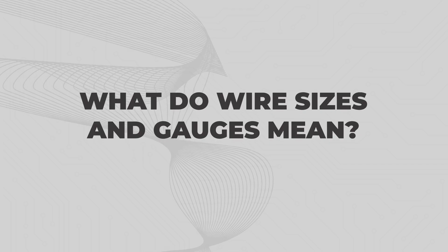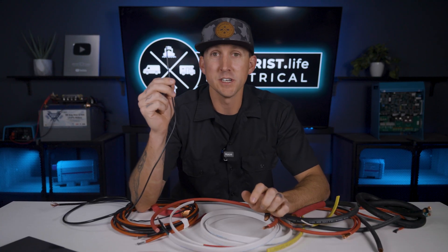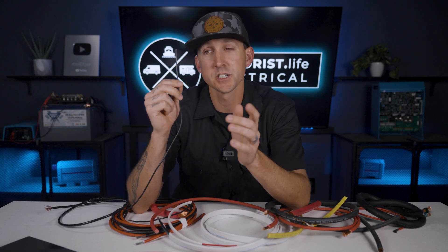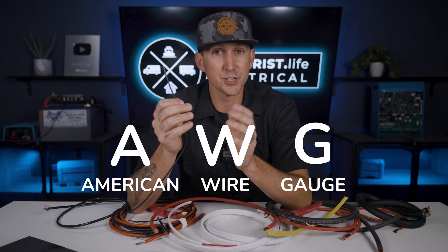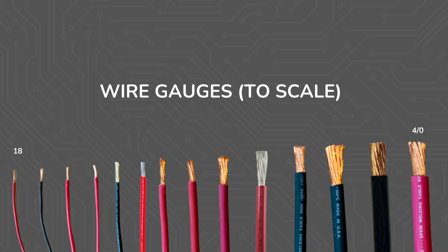What do wire sizes and gauges mean? In the United States, the smallest wire that we typically use in a mobile, marine, or off-grid electrical system is 18 gauge, which is abbreviated AWG for American Wire Gauge. The largest size is four ought, and here's a to-scale graphic of what it looks like in between. From smallest to biggest, we just start counting backwards by two: 18, 16, 14, all the way down to two.